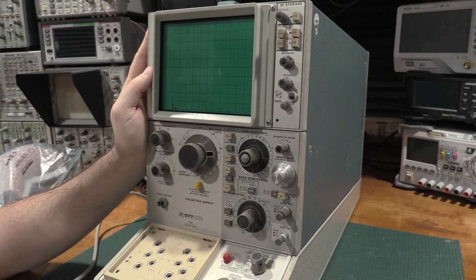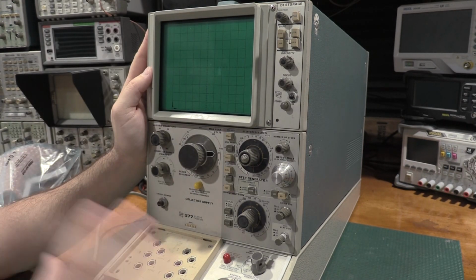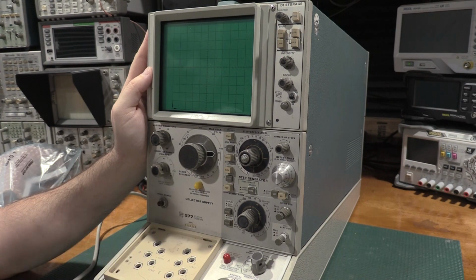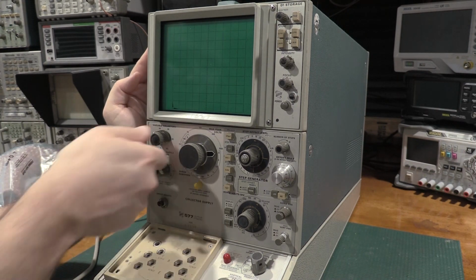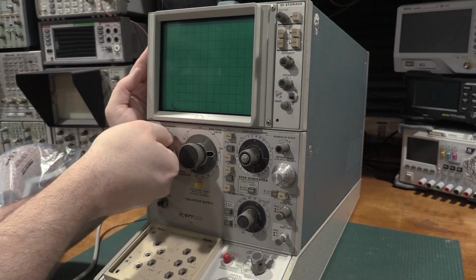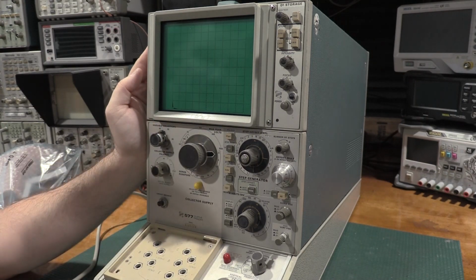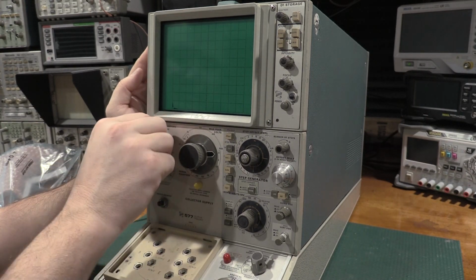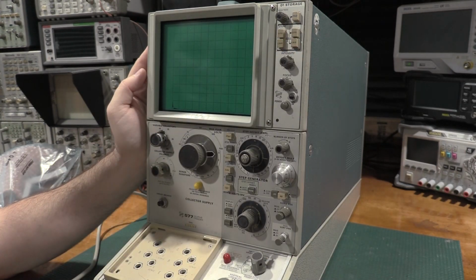So first things first, on this one we have a D1, which is the storage flavor. There is a startup routine for this. If you're unfamiliar with storage tubes, we'll take the variable collector and pull it all the way down to nothing. This knob's a little busted. I'll have to do something about that. We'll turn the intensity down to nothing. We'll focus it, defocus the tube. We'll turn the brightness down to nothing, and we'll power the unit on.